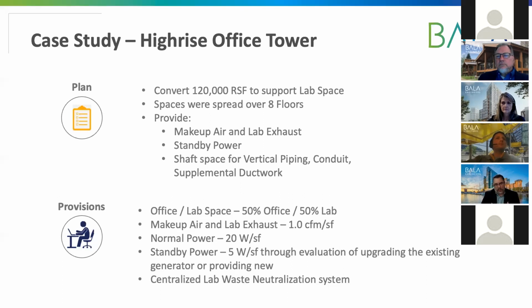And what we found as we were developing the fit out, from our initial first pass of the potential tenants' needs, we saw that we're going to consume half of our utilities, airflow, power, just with 2 floors. So it was nice that we were able to work with them on the core shell side, highlight that fact, and then work with the lab users to really think about how they want to use their space. So through programming, we're able to then reevaluate. And in this case, we basically were able to reduce the amount of fume hoods they're initially looking for so that we could keep the first 2 floors back to a prorated amount of the total volume of the 80,000 CFM I mentioned earlier on the exhaust. But we were able to utilize that as a tool to keep right sizing the floors, and that will continue as we go up the building.